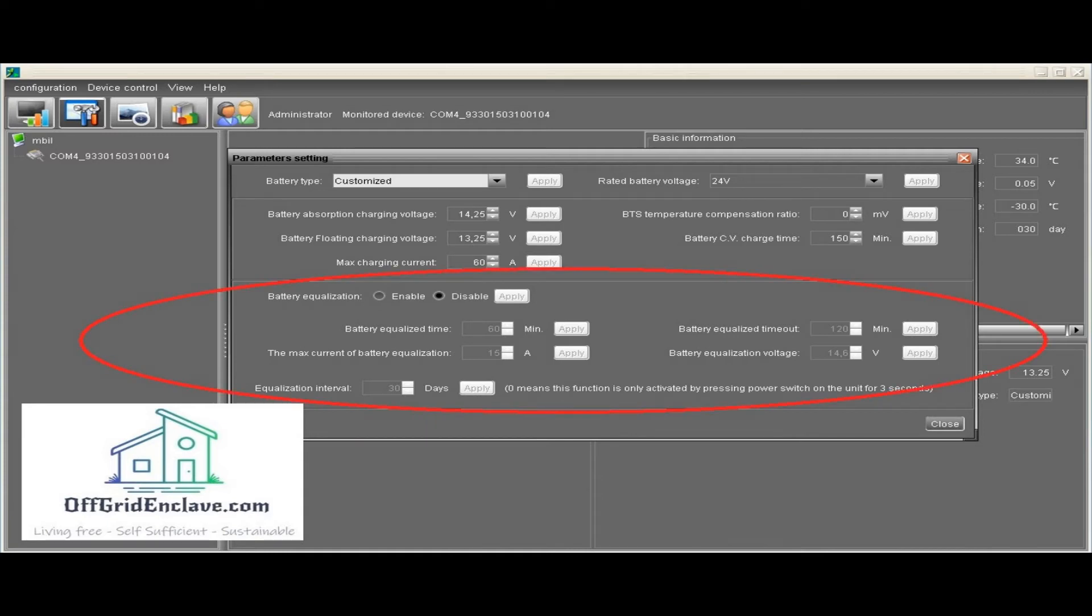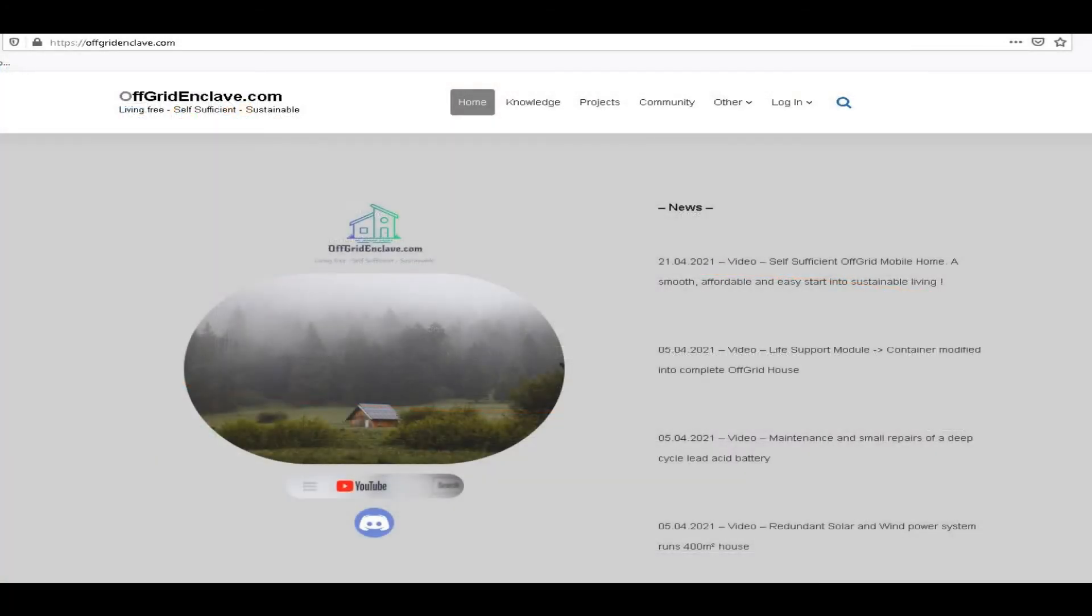In the parameter settings window you can customize all important settings of the charge controller: absorption voltage, float charging voltage, the maximum charging current, and you can also configure the temperature compensation ratio here. Furthermore there is an option to enable battery equalizing, with plenty of options to configure that according to your needs.